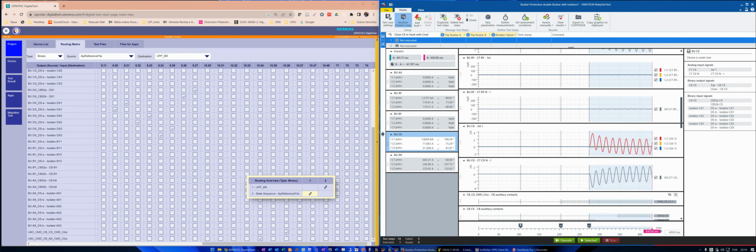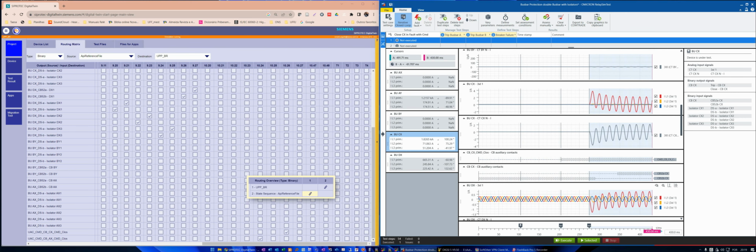And to show all this interaction, I will show here. In the first step, we didn't apply the fault. We apply the fault here in the second step with my bay open. And in this third step, I give the close command to my bus bar protection that was linked here. And we can see here the circuit breaker will be closed because of this step of the simulation. And I put a time between my command and the close command of the circuit breaker.